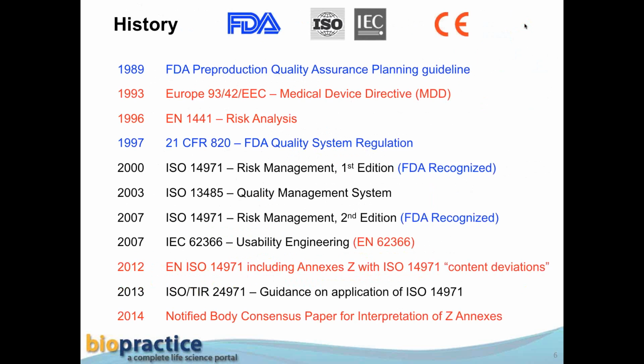And I'm only showing one up at the top, 1993, the Medical Device Directive, which applies to most medical devices. There's two other directives, but all of them have some requirements related to risk that are more stringent than the principles in 14971. And so in 2012, those differences, the more stringent requirements for the directives, were pointed out in the EN ISO 14971 2012 standard.